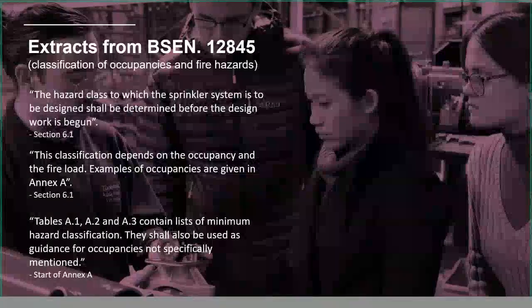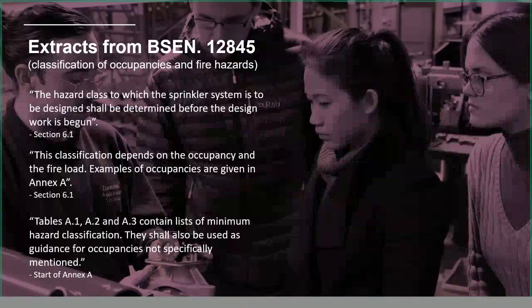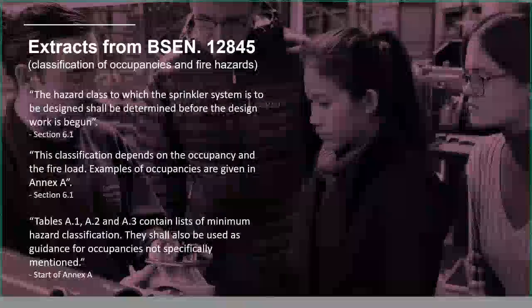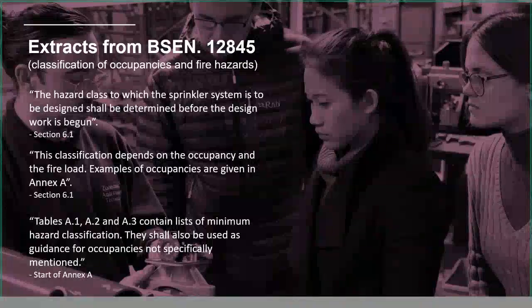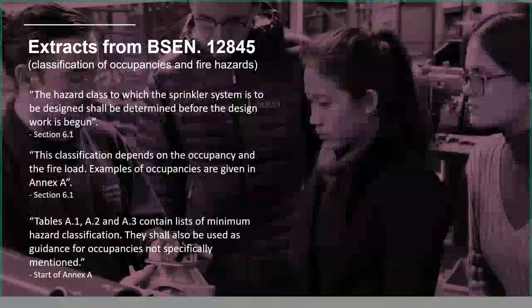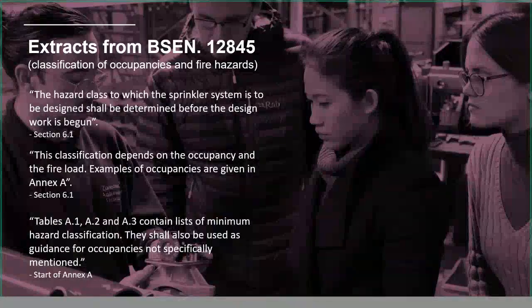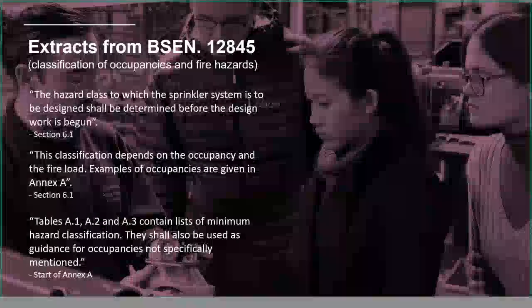The hazard category is one of those things that must be settled first. The classification depends on the occupancy and the fire load — examples are given in Annex A. Fire load is a big part of determining hazard category. For industrial applications, storage is a major factor; if you're storing a lot of goods, you have a high fire load — things that are likely to cause or fuel a fire.